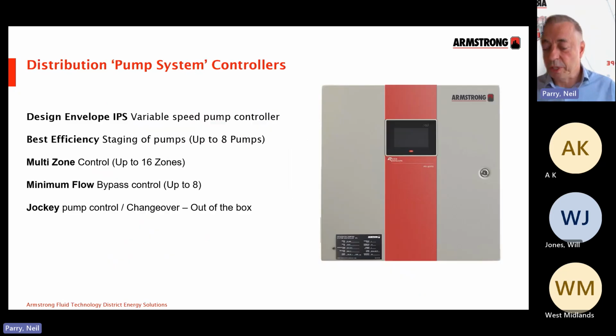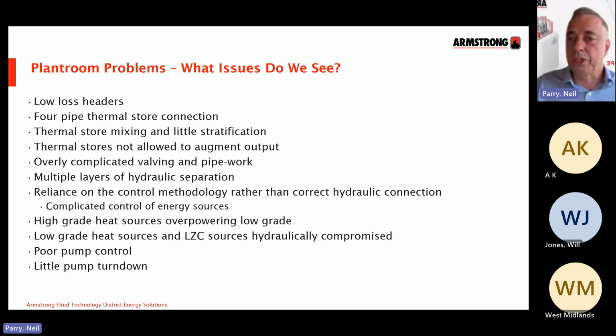If you have a system that needs more than 4 pumps, we have a controller that can control 8 pumps up to best efficiency staging points. And that controller can also control zones and bypasses on the network as well. And if you need to, it can actually control a jockey pump as well, with all the caveats I mentioned earlier on. So when we look to the plant room, what issues do we see?